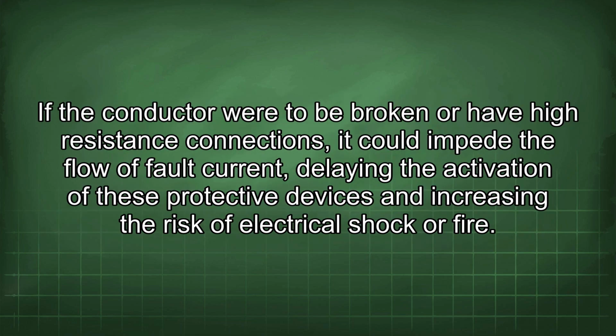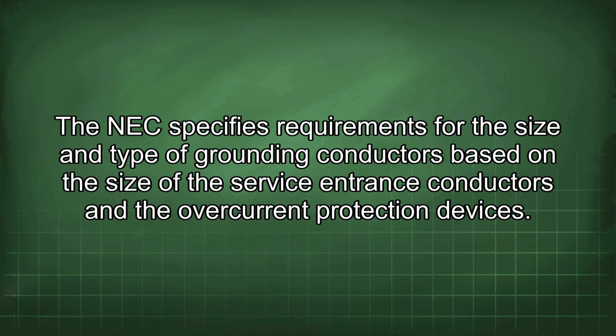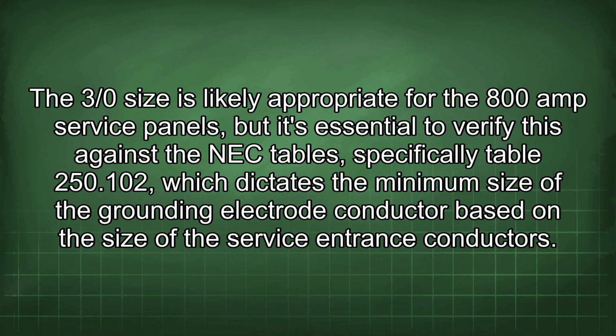If the conductor were to be broken or have higher resistance connections, it could impede the flow of fault current, delaying the activation of these protective devices and increasing the risk of electrical shock or fire. The NEC specifies requirements for the size and type of grounding conductors based on the size of the service entrance conductors and the overcurrent protection devices. The 3/0 size is likely appropriate for the 800 amp service panels, but it's essential to verify this against the NEC tables, specifically Table 250.102, which dictates the minimum size of the grounding electrode conductor based on the size of the service entrance conductors.